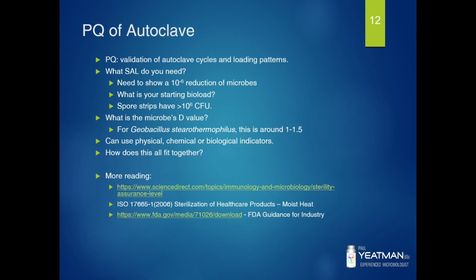So with the spore solutions, production would bring up bungs, and we inoculate the bungs with a known volume of spore solution, which has a known volume of microbes. And once that's dried, of course, according to your validated hold time, those bungs get sent back down to production. They go through the autoclave cycles. The bungs get brought back up to the lab. You fish out the bung that's been inoculated, which you can tell because it's a different colour to the rest, or you've labelled it a certain way. And you put those bungs into TSB and determine whether or not anything grows.